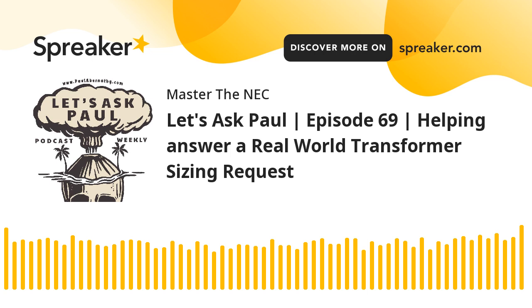It says, do I need a disconnect at the HVAC unit, fused or non-fused? I think you'll find that you most certainly need the disconnect because the rules tell you that you have to have a disconnecting means in Article 440. But in your case, because of your secondary conductors and because you're wanting to use this secondary conductor rule, you're going to have to terminate into a circuit breaker anyway. And of course, you still need your protection for your HVAC, and you follow the nameplate, minimum circuit ampacity, maximum overcurrent protection. So it just takes care of itself. So I think that covers you.